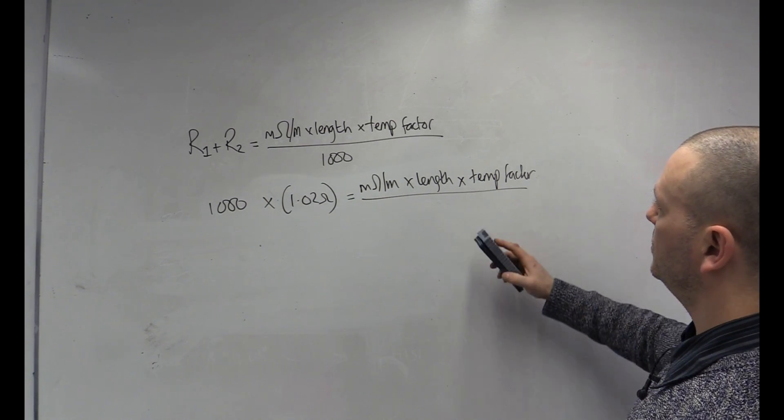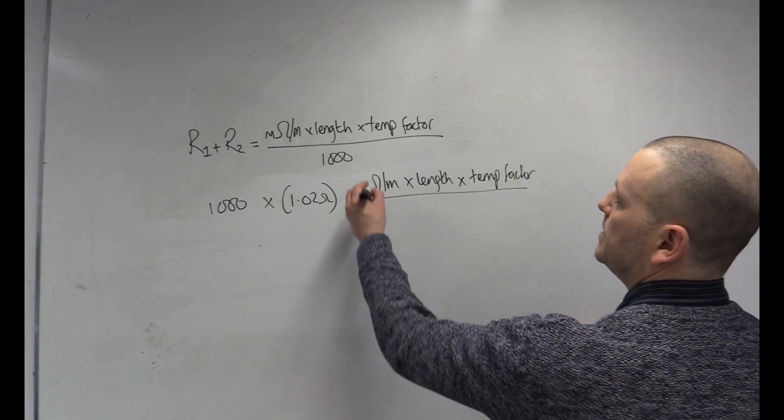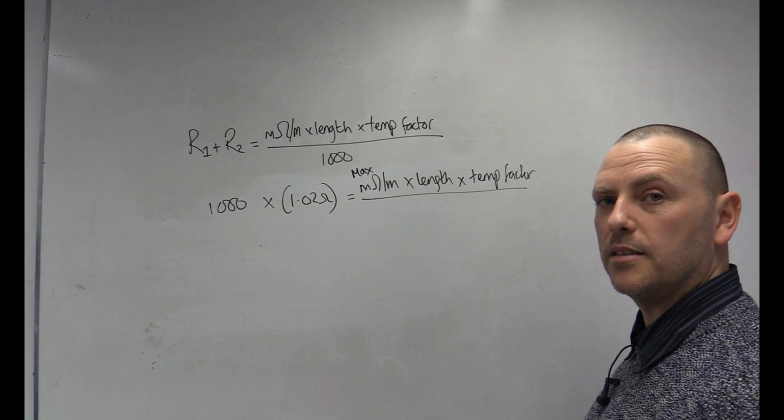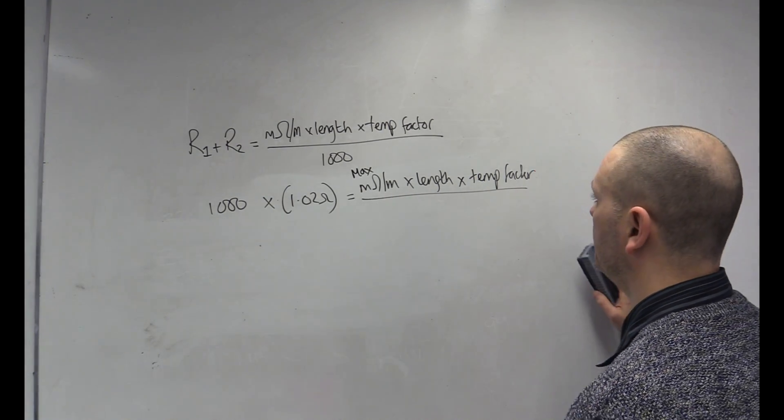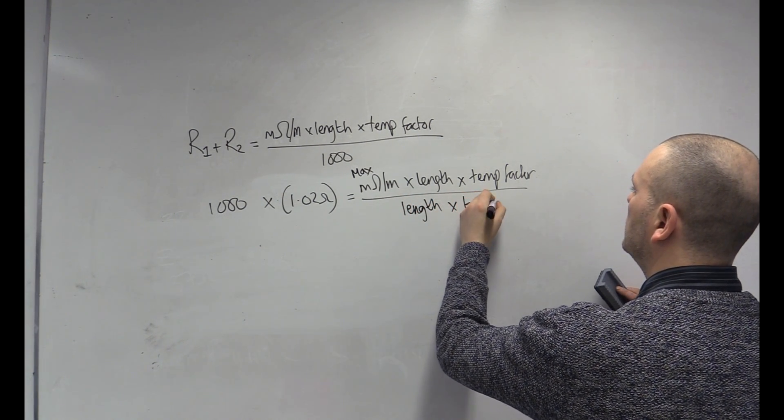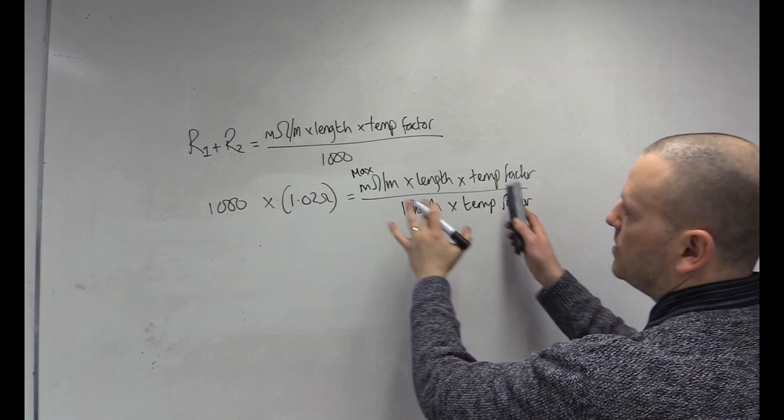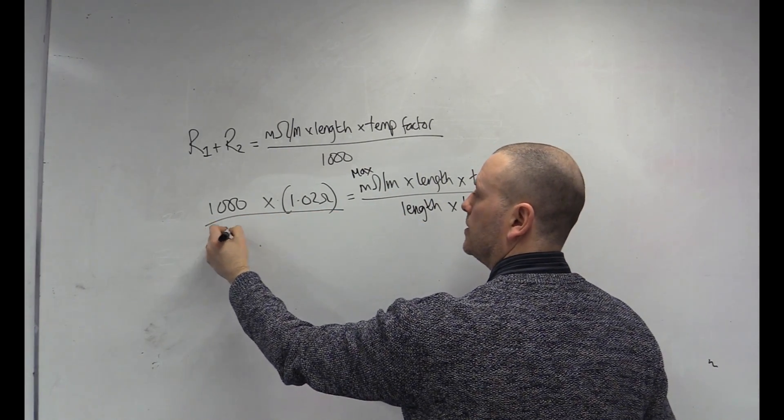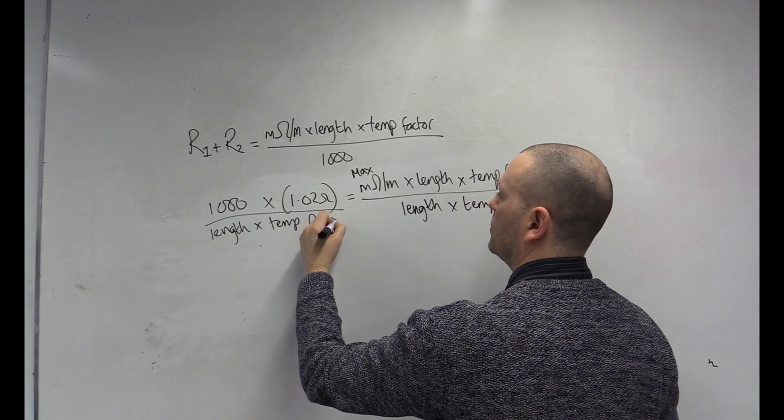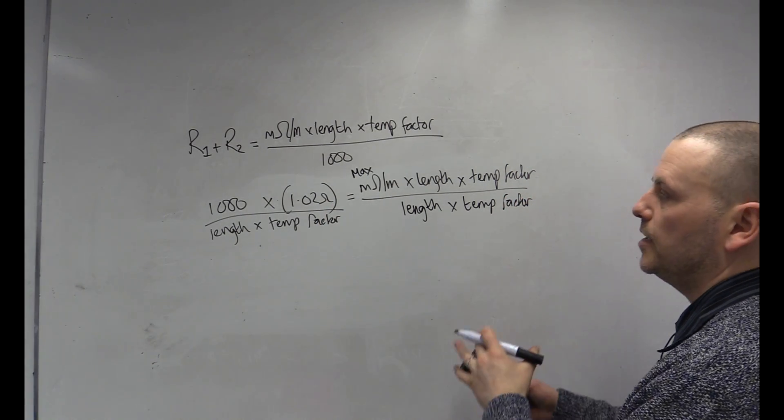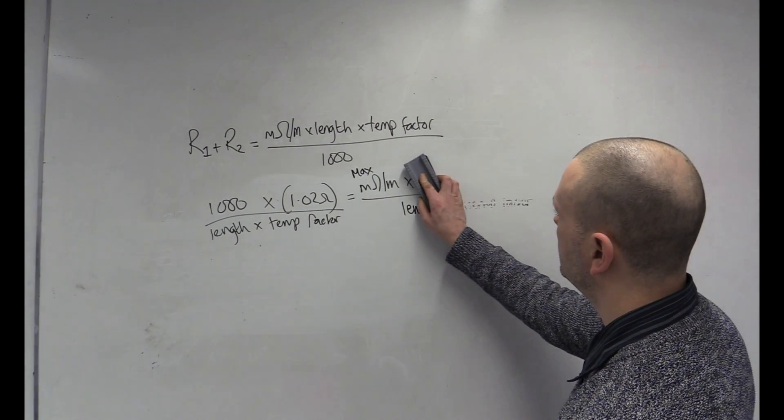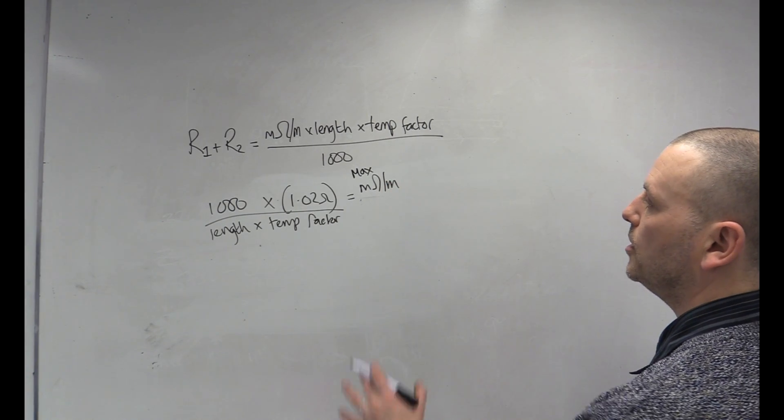Now, we need to isolate milliohms per meter. Incidentally, this is going to give us our maximum milliohm per meter. Now, all of these things are being multiplied at the same time, so we can divide them out at the same time. So, that's exactly what I'm going to do. So, length, temp factor. I've unbalanced it. I've got to copy it. Length times temp factor. Now, we could put some values in from the example before. So, let's just tidy this up. We've got our equation here.